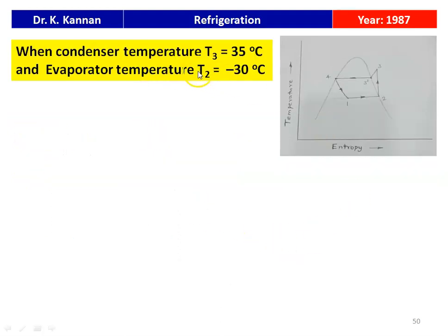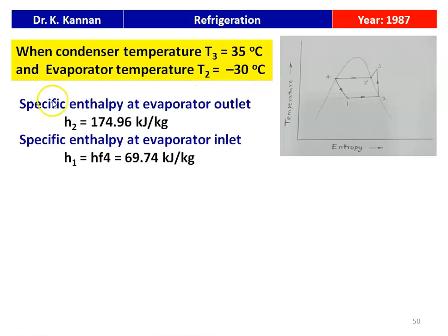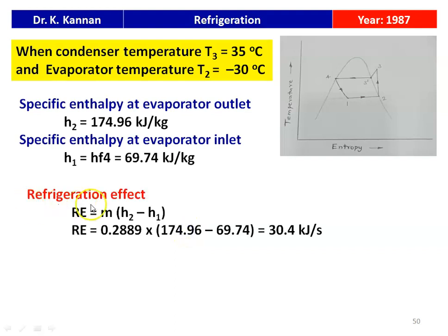When the evaporator temperature is altered to minus 30 degree Celsius (condenser temperature unchanged at 35 degree Celsius), H2 changes to 174.96 kJ/kg while H1 remains 69.74 kJ/kg. The new refrigeration effect equals M multiplied by (H2 minus H1): 0.2889 multiplied by (174.96 minus 69.74) equals 30.4 kJ/s. The refrigeration effect for the modified condition is 30.4 kJ/s.